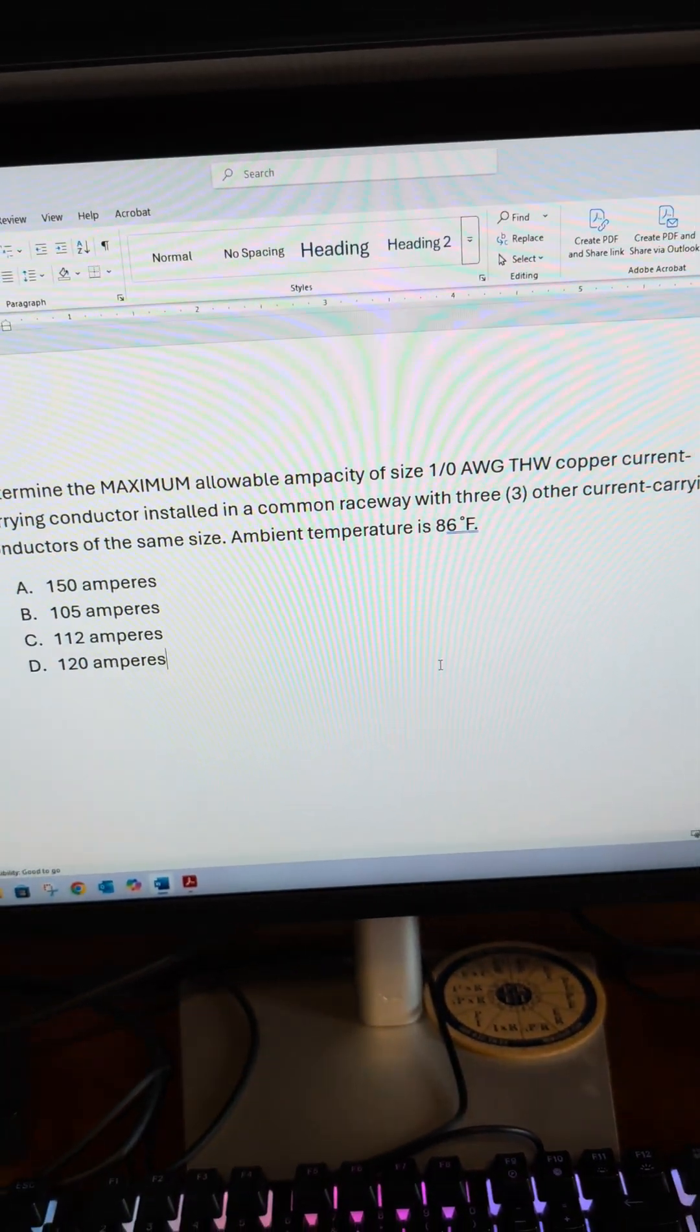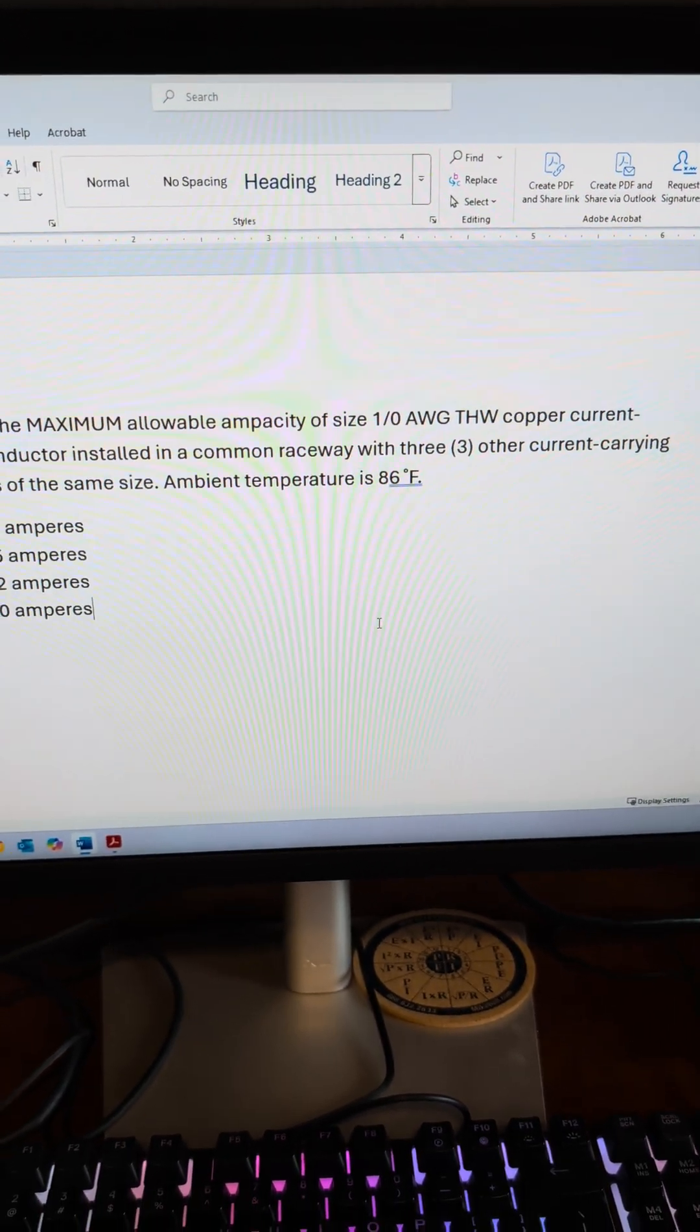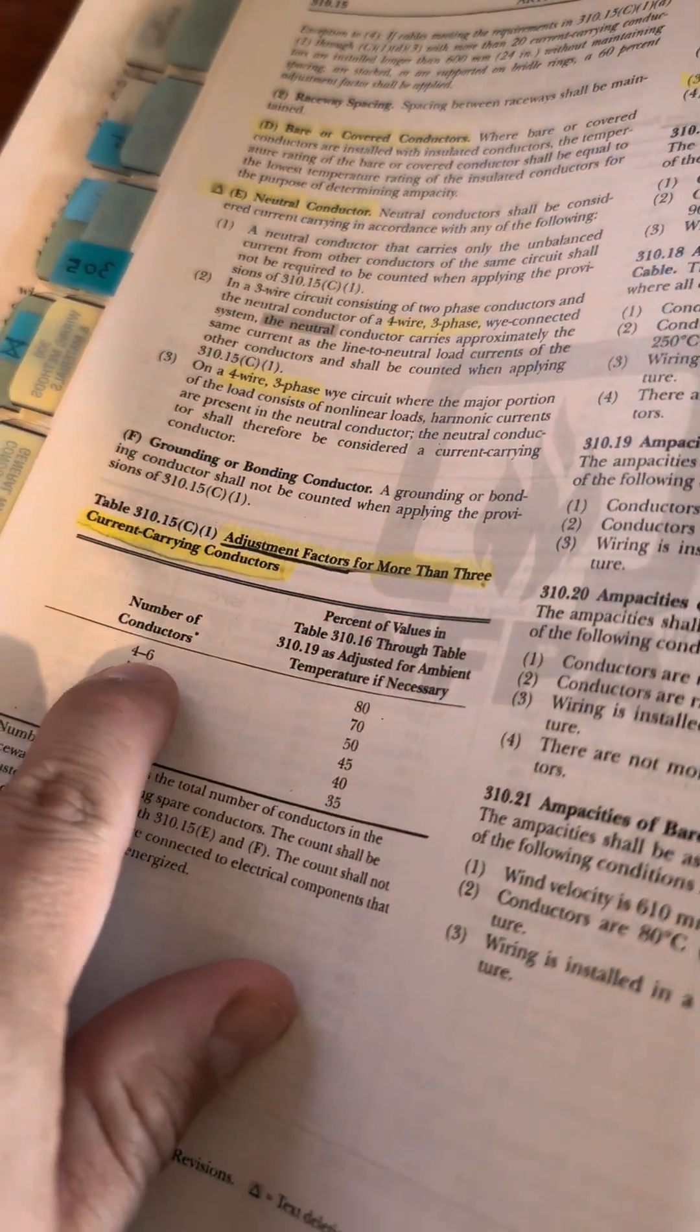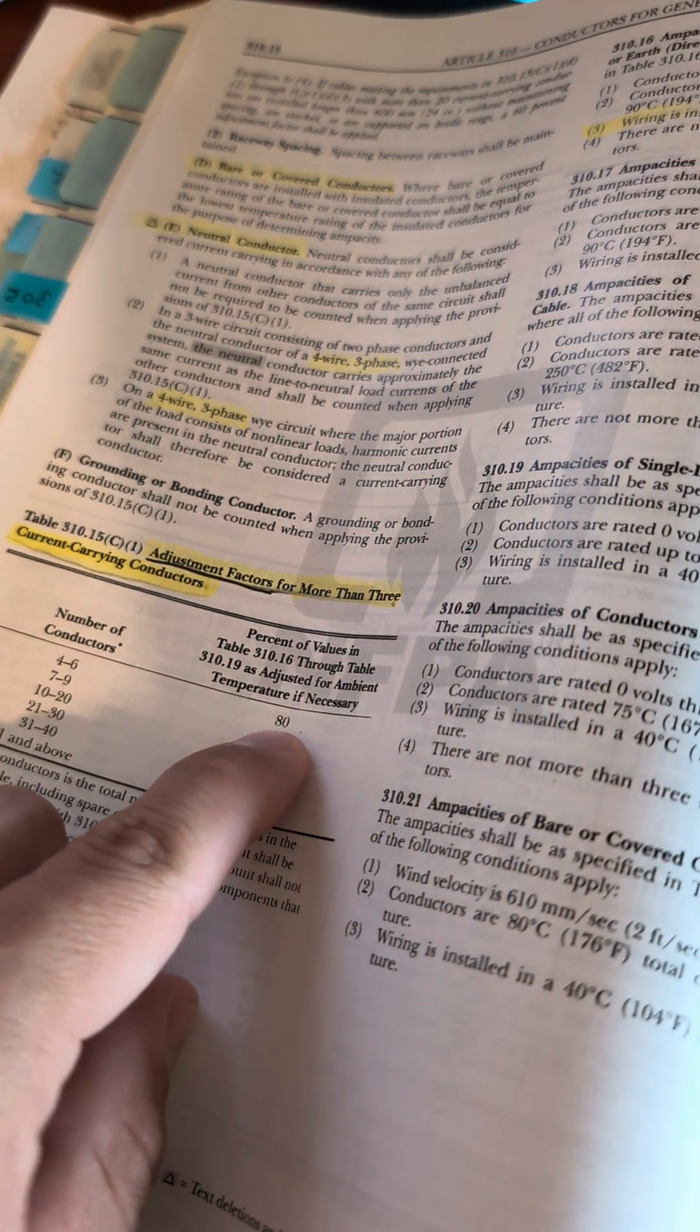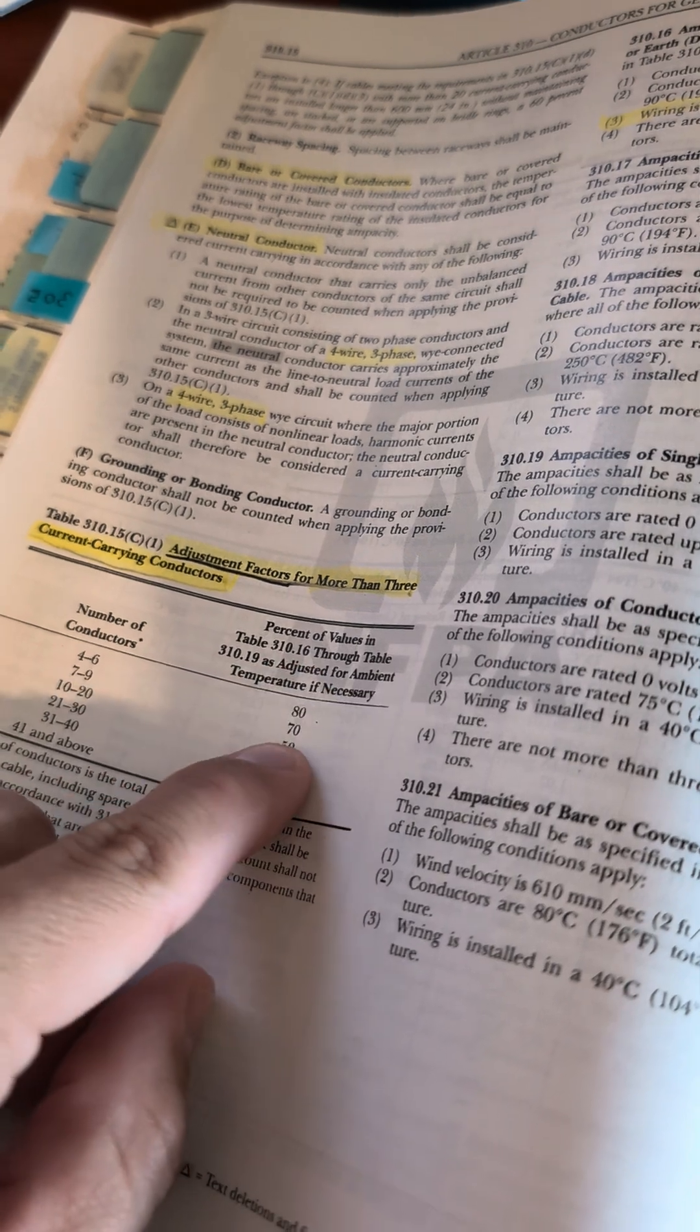Next, we need to adjust for more than three current carrying conductors. We know we have 1/0 with three others, meaning there's four total, and so we have to adjust our amperage rating on Table 310.16 by 80 percent.